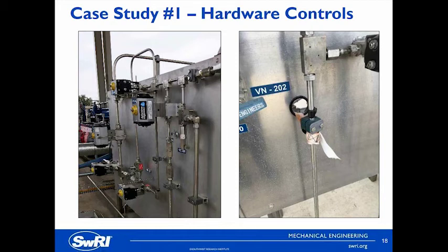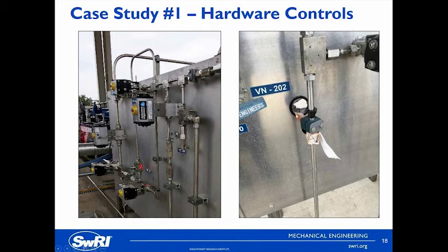The next hardware control is restraints for tubing and piping. We have some tubing that is one inch or less, two inch piping, and some hoses in this facility. You can see that most of our tubing has Stauff clamps that are physically welded to a panel. For areas where we don't have as rigid a mount, we've used something called a hose hobble — it's a nylon hose with a Stauff clamp. The tape is actually recommended by the manufacturer. The intent is that if this connection were to come apart — this is a 20-foot piece of tubing — the hose hobble would get caught on the Stauff clamp, which would get caught on the tape and would stop the piece of tubing from becoming a whipping hose. At these pressures, that is definitely what happens.